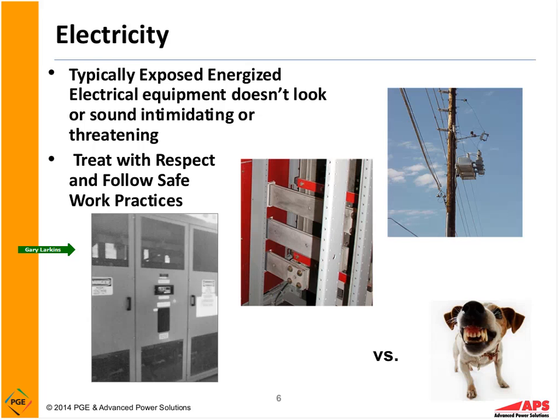Now in the middle picture here we have exposed bus work. So this is a grounded surface right here, part of the switchboard, and right here is the exposed bus bar, 277 volts to ground, 480 volts phase to phase. Definitely a hazard when energized. And of course, we have overhead lines here, where if we get too close to those overhead lines, or make contact with them, whether it be bodily contact or with some type of conductive material such as a wet 2x4, tree branch, etc., we can definitely experience the wrath of electricity.